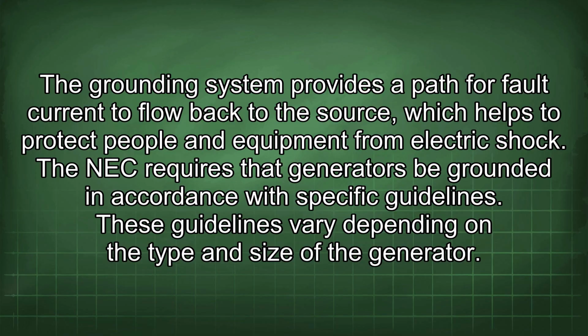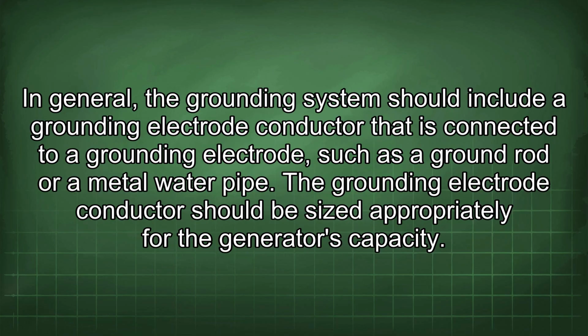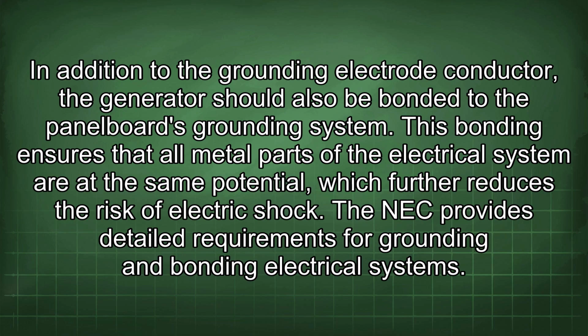The NEC requires that generators be grounded in accordance with specific guidelines. These guidelines vary depending on the type and size of the generator. In general, the grounding system should include a grounding electrode conductor that is connected to a grounding electrode, such as a ground rod or a metal water pipe. The grounding electrode conductor should be sized appropriately for the generator's capacity. In addition to the grounding electrode conductor, the generator should also be bonded to the panel board's grounding system.